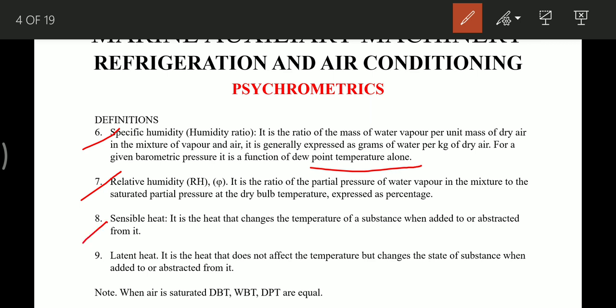Sensible heat is the heat that changes the temperature of a substance when added or abstracted from it. Latent heat is the heat that does not affect the temperature but changes the state of the substance when added or abstracted from it. One important point: when air is saturated, the dry bulb temperature, wet bulb temperature, and dew point temperature — all three temperatures are equal.